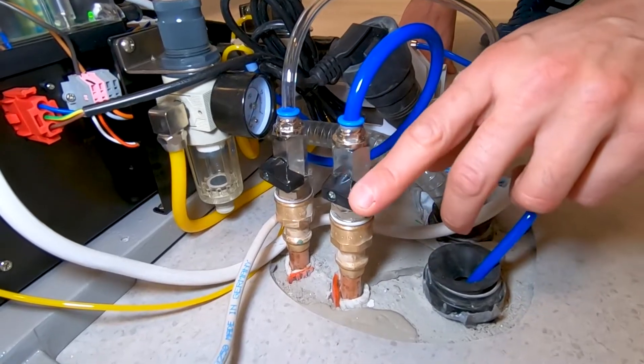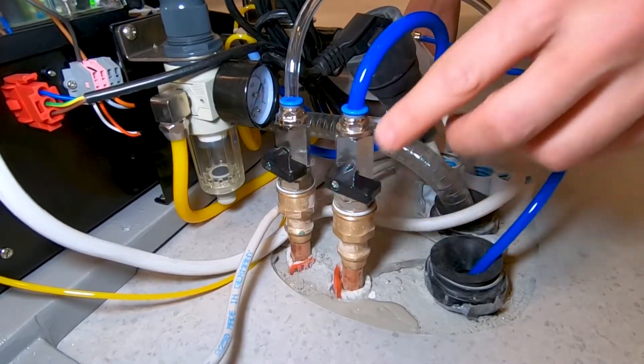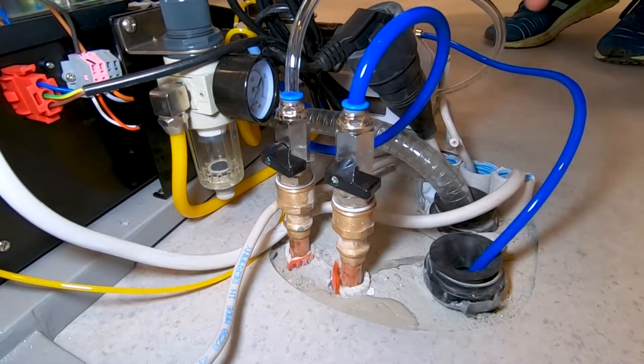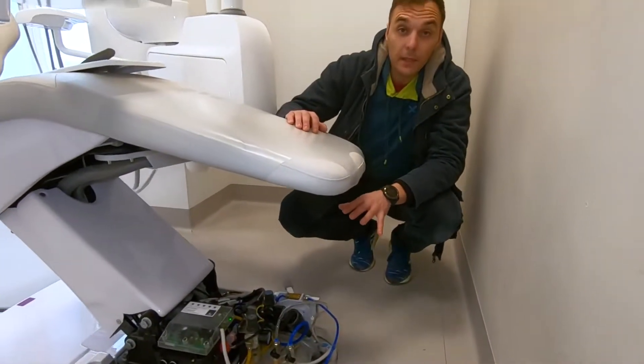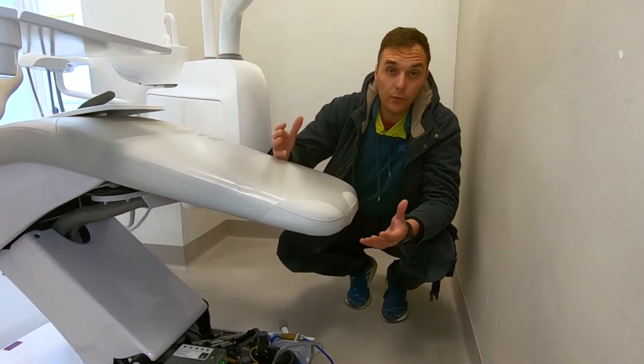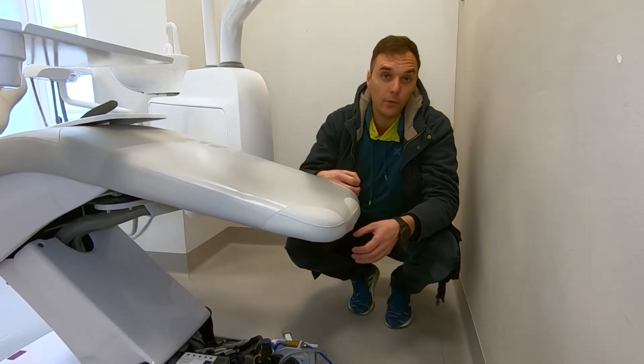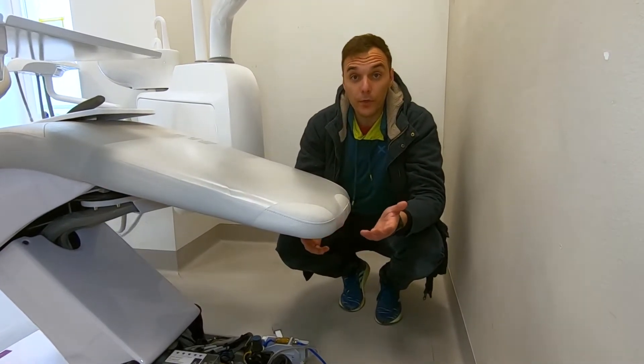It's always good to apply this kind of valve to open and close the air and the water. So in case you have a problem on a dental unit, you can immediately close the water and the air and act on the dental chair. This is a typical installation that we do when there is a spit-on ball valve and the water unit, and of course only one tube that goes to the suction. Thank you for watching this video.